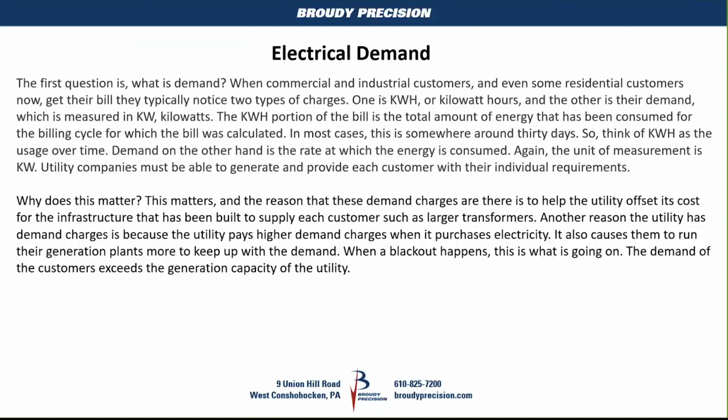The reason that the demand charges are there is to help the utilities offset the costs for the infrastructure that has been built to supply each customer, such as larger transformers. Another reason that the utility has demand charges is because the utility pays a higher demand charge when it purchases electricity. It also causes them to run their generator plants more to keep up with demand.